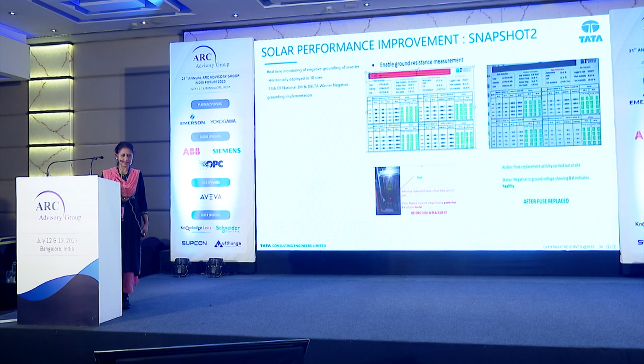This is real-time monitoring of negative grounding of the inverter, which happens more often during rainy seasons due to aging. We introduced a safety fuse in this circuit with some automation, so in case of negative grounding, the fuse blows and we know it in our SCADA system. Based on this data, the fuse can be replaced, which also prevents the inverter from degradation.